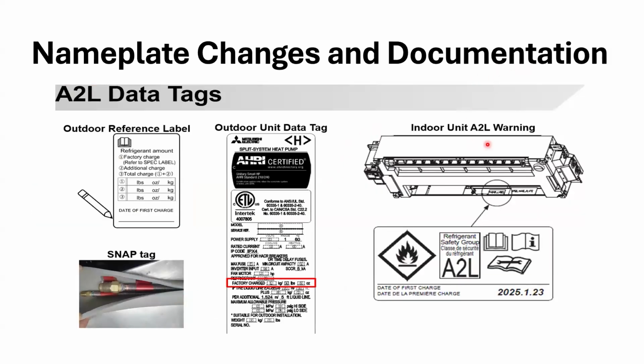So, nameplate changes and documentation again. Here, that's the MLZ, the one-way cassette, and up on the chassis of the units is where they're going to have that A2L refrigerant safety and handling labeling. Here's an outdoor unit data tag. Factory charge is listed down here. Then the outdoor reference label, with the refrigerant amount. Most of our units used to have this label, but no one ever filled that information in. I think it's required more so than ever to have that information filled in here. Plus, it helps us. Obviously, it's nice to know if you're doing a repair on the system that someone put the total charge listed somewhere. And then on the indoor unit, on the flare connections right there, those are called the snap tags, and the red there designates the 454B refrigerant. So, just identifying that.